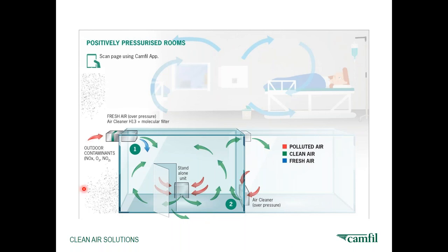The concept of creating positively pressurized rooms is to ensure that the air introduced to the room is clean and that any air that does escape will not affect other patients or staff. In hospitals, the quality of air introduced into the room is not only important for the patient within the room, but also for the doctors and nurses that work in the room. In the square box, you see a room within a building and its different air pattern.